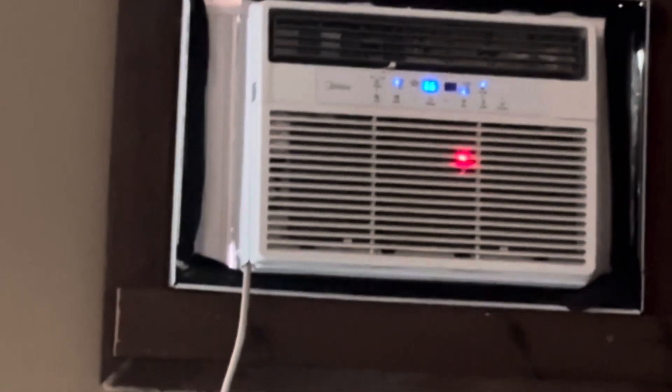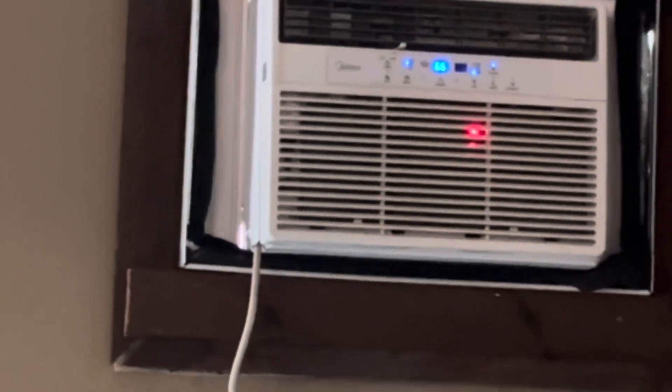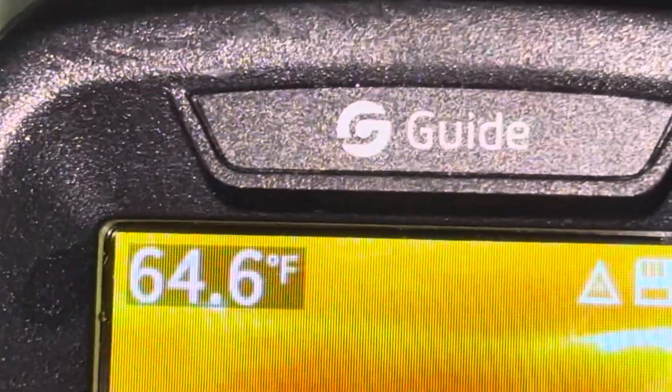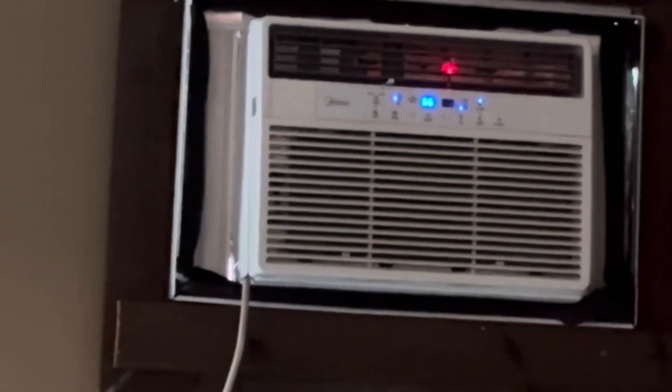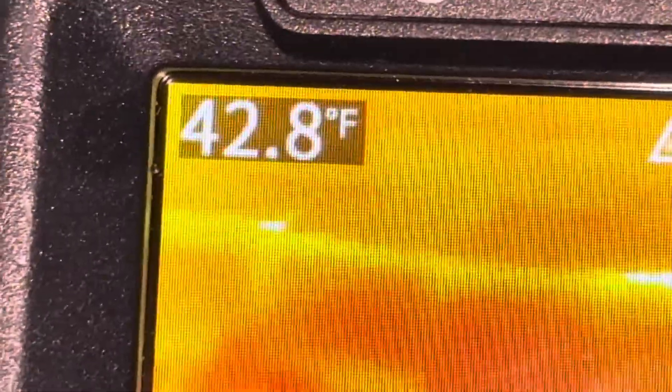The other trigger actually has two functions, but if you have the laser turned on, it turns on the laser and you can see we're picking up 64 degrees from that return of this air conditioner. If we move it up to the supply of the air conditioner, it's giving us 44, 42 degrees.